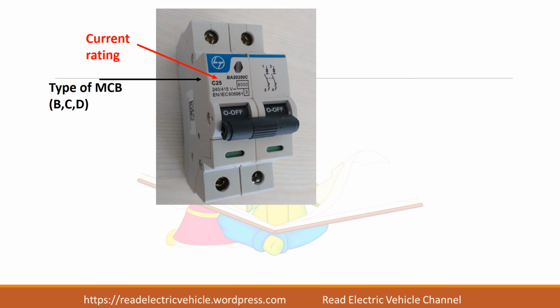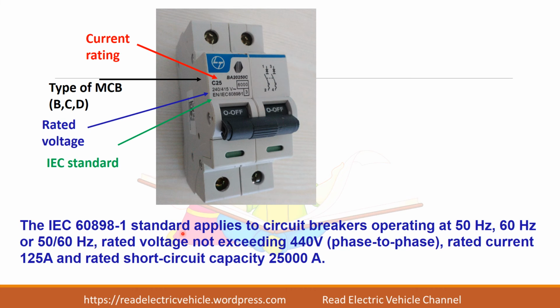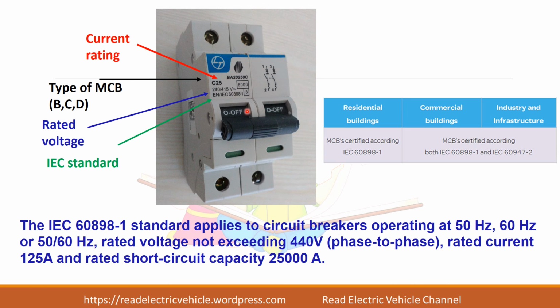So we have seen about the current rating and type of MCB. Next we have the rated voltage or the operating voltage of this particular MCB. Then we have the IEC standard printed on it. It means that this MCB has been subjected to the different tests specified by this IEC standard. Normally this IEC standard is applicable for breakers operating at 50-60 Hz, 440 volts, rated current 125 amps and short circuit current of 25 kilo amps. So this breaker is suitable for residential purpose.